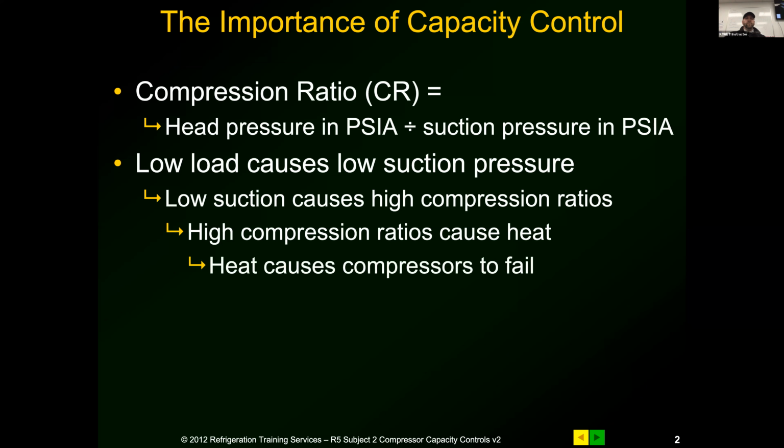Heat causes compressors to fail. The two biggest failures of compressors are excessive heat and voltage issues. So that's what we deal with in this. Any manufacturer will tell you what keeps compressors alive: cool gas.